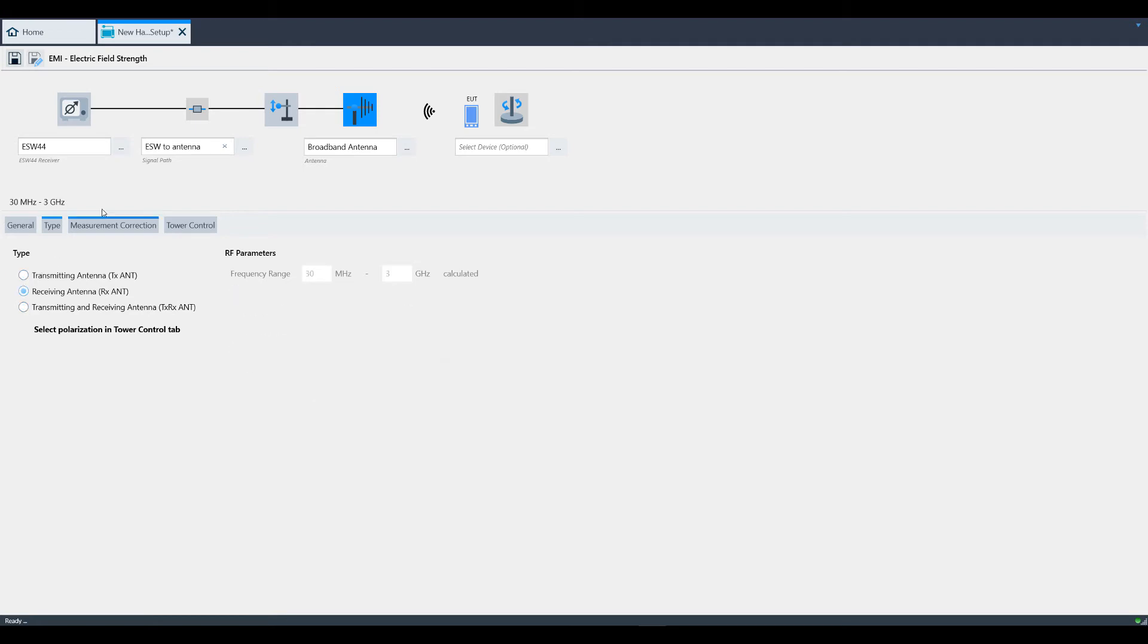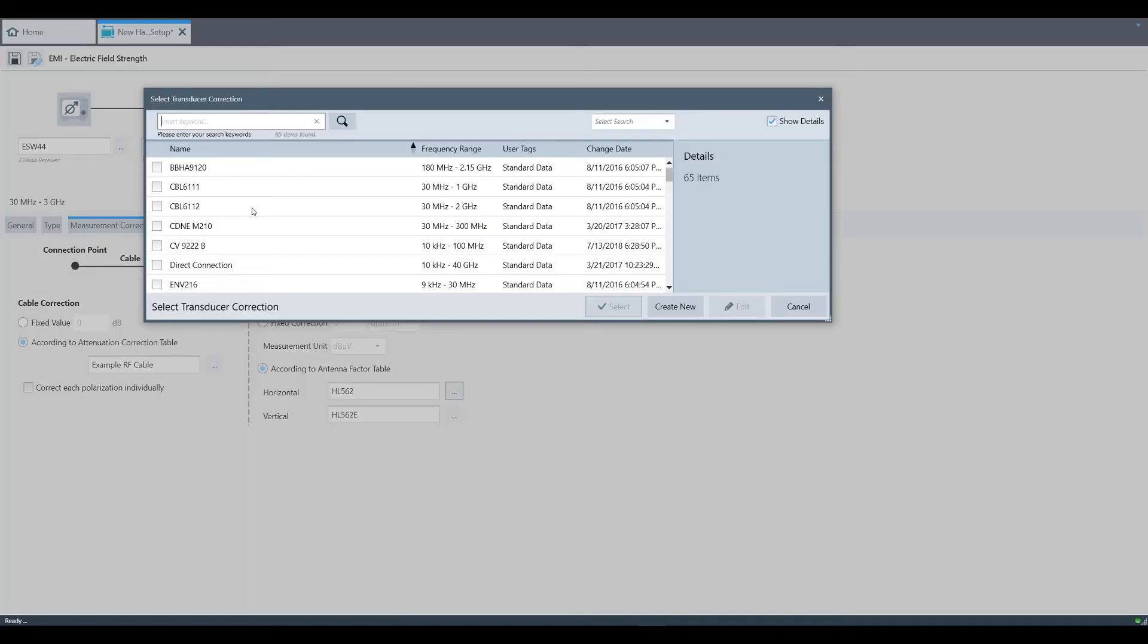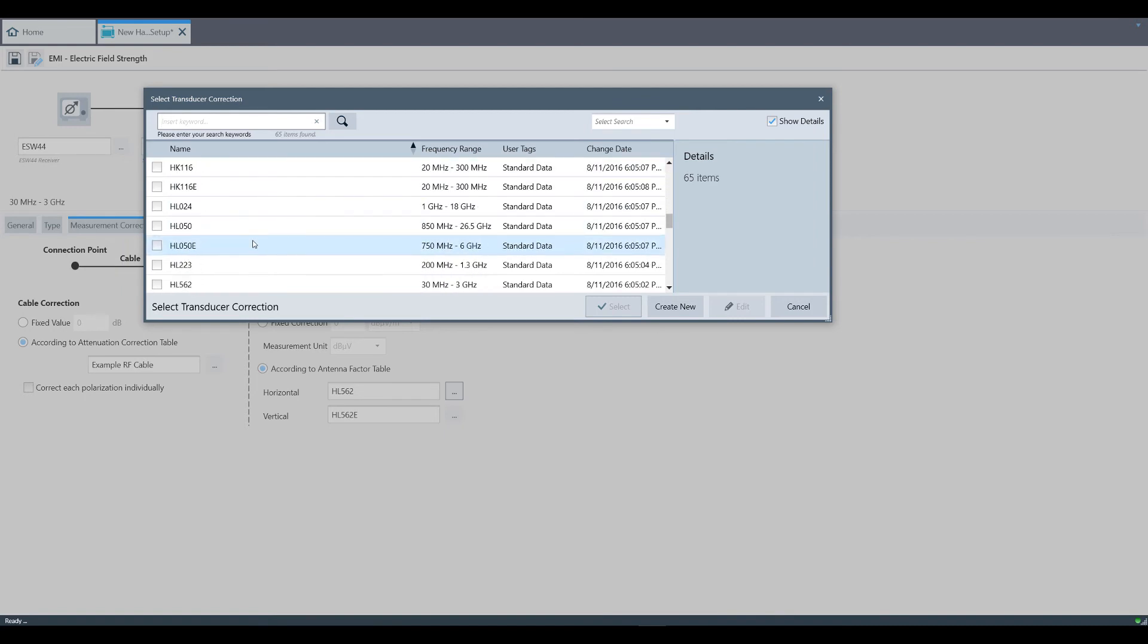Under Measurement Correction, if you have additional attenuation factors that you want to include as part of the antenna but not in the signal path, you can apply them here. On the right side, under Antenna Factors, you would select your antenna factor for both horizontal and vertical polarizations.